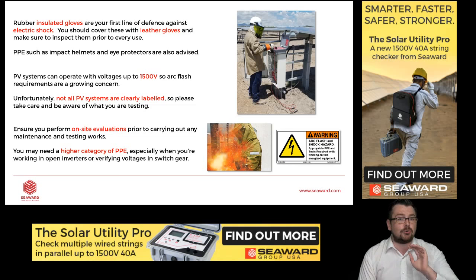Finally, before you arrive on site, we should really perform an on-site evaluation with regard to safety. A lot of new construction of solar farms, of course, they have health and safety officers on site. All the risk assessments have been done. But if you're a subcontractor and you've been asked to go to a legacy site and there's been no on-site evaluation of health and safety done, you should really request that, because your health could be at risk, particularly if, as I mentioned earlier, there is no idea of what the string configuration is and the level of electricity that you're dealing with.